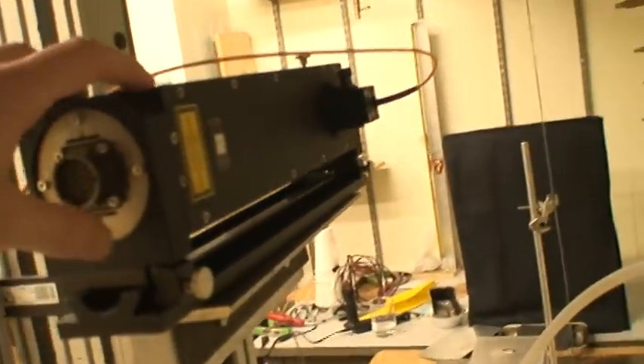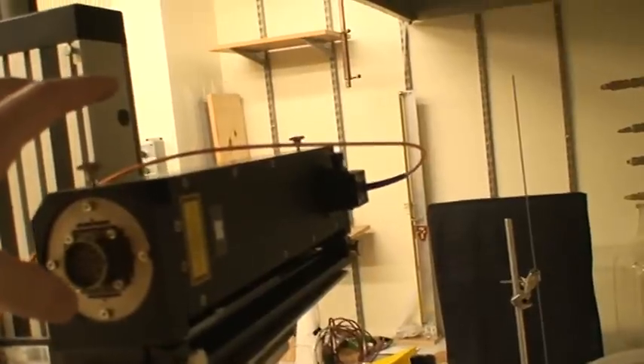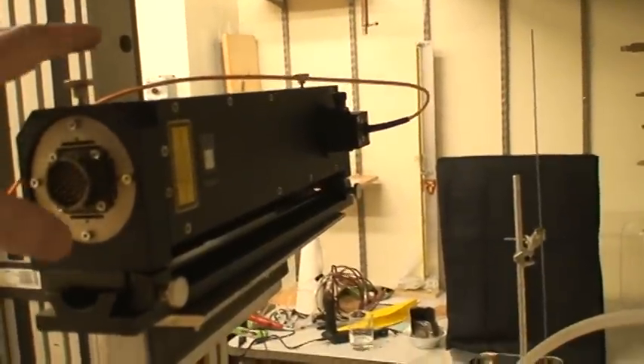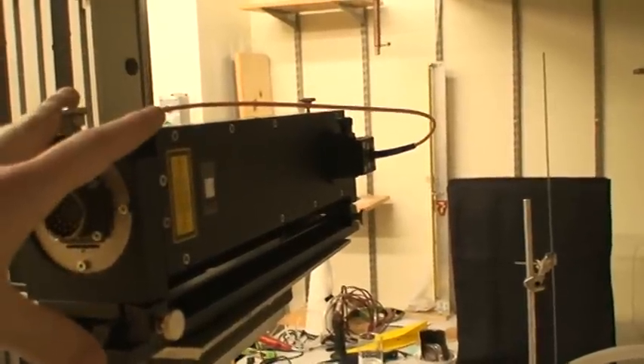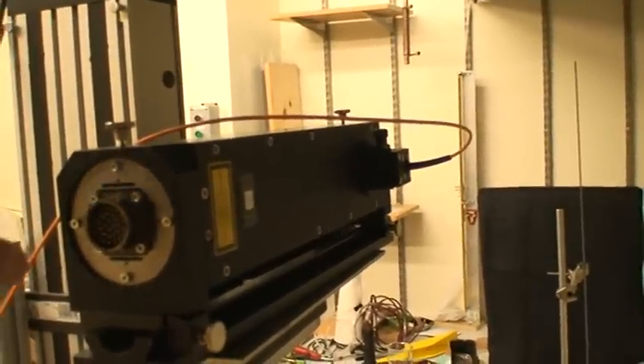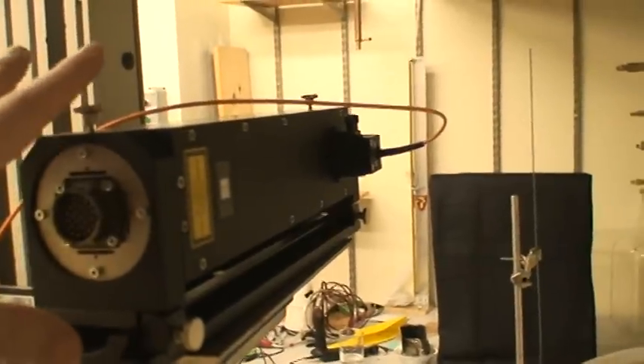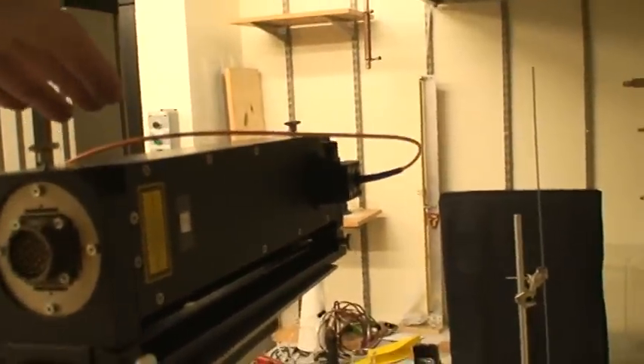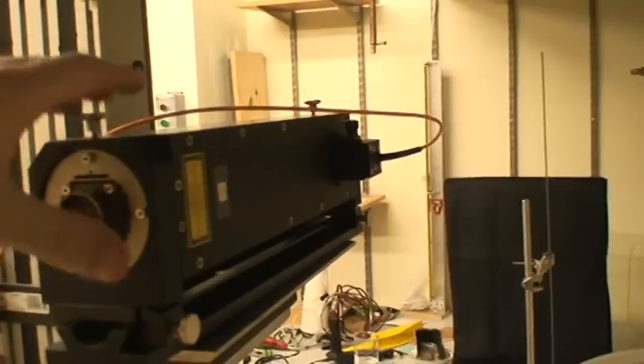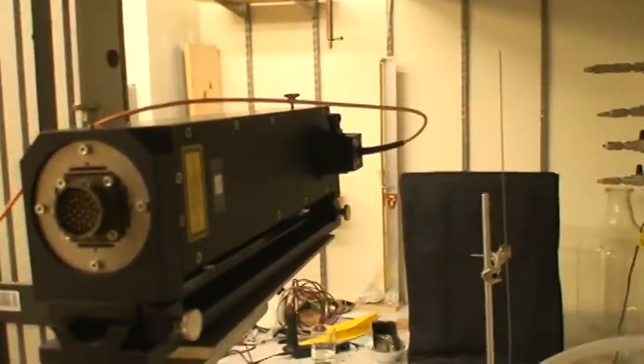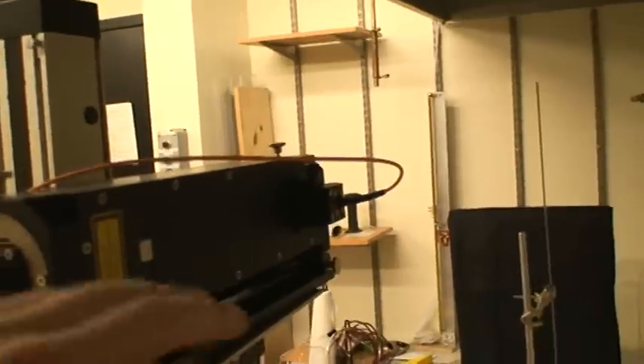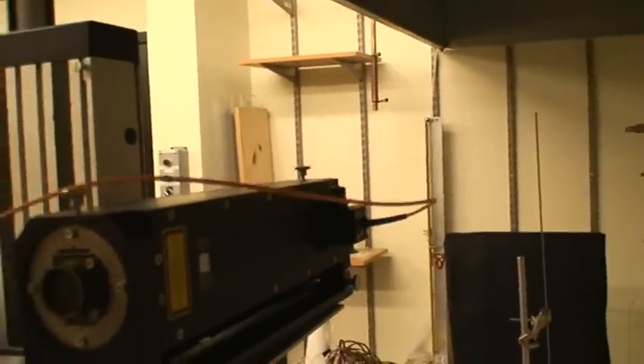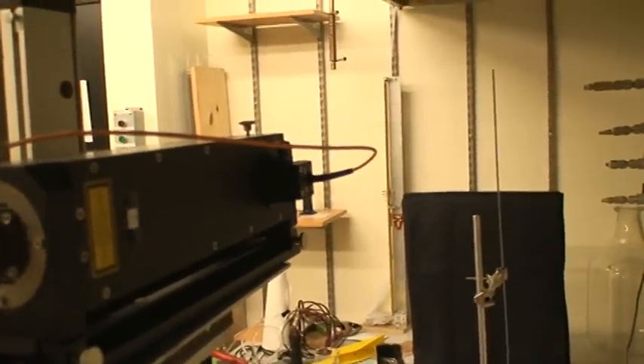We're using this in a combustion lab. If you're using the laser to measure the flow above a fire, we were doing it originally—you want the heat. This case is a heat sink, so you want to keep the case cool. If the case gets hot, then the laser can't cool itself and it'll overheat. You have this optical fiber. You want to make sure the optical fiber doesn't bend or kink or get stepped on or get crushed.